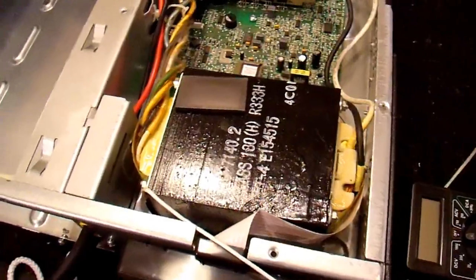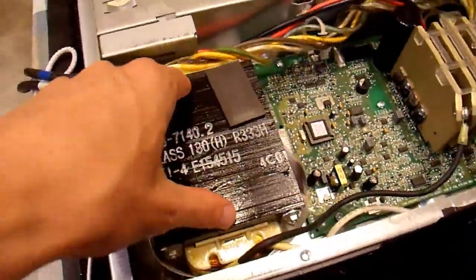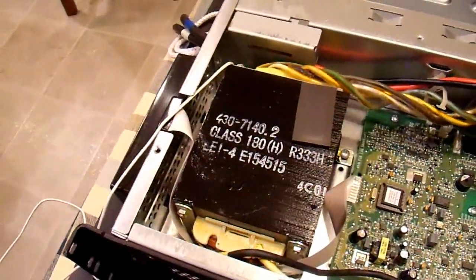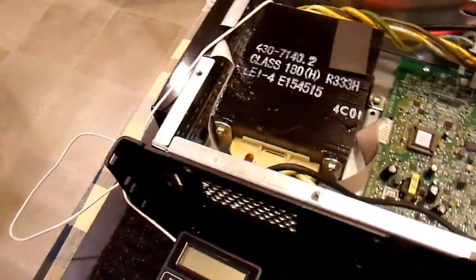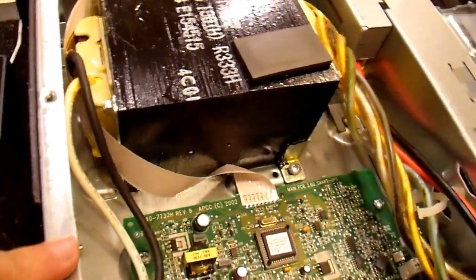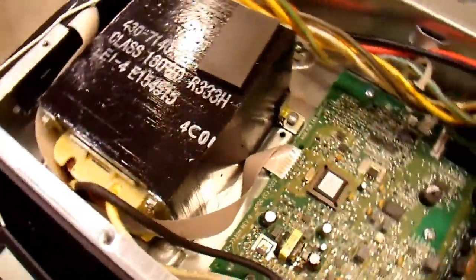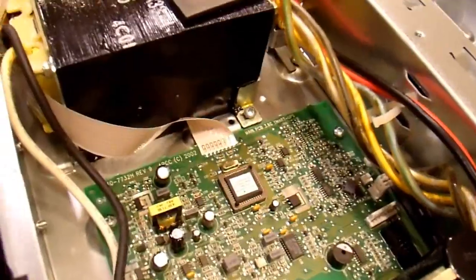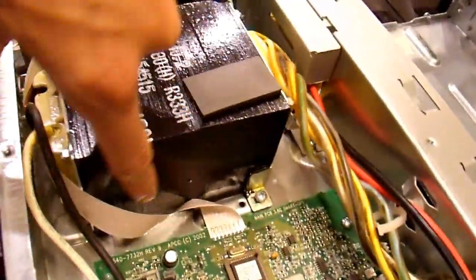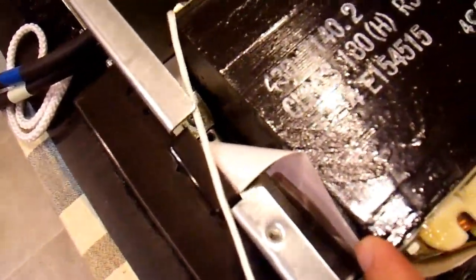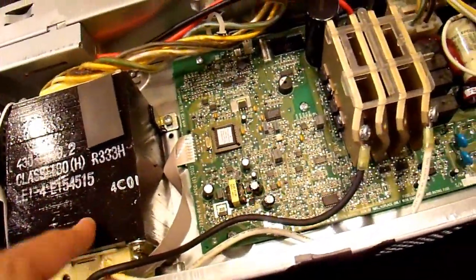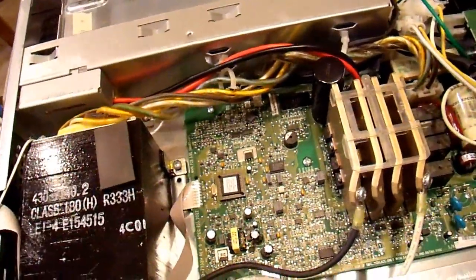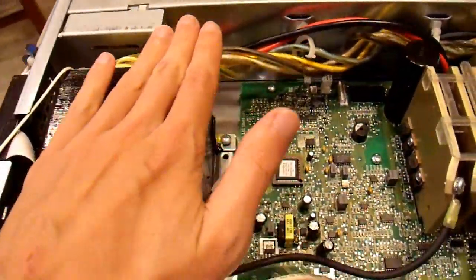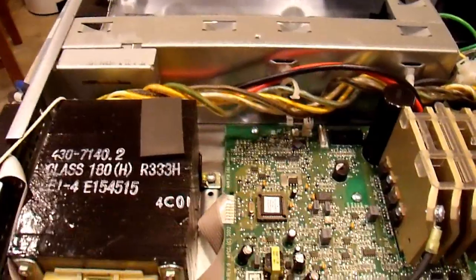So for the first problem, the transformer overheating, I thought a little bit about what to do to keep that cooler. I looked at how it's held into the unit, how the air flows over and under it, and basically the only surfaces that can be cooled by airflow is this surface right over here, and maybe a little bit on the back if the air wraps around. But the bottom, there's no airflow, and the top, there's the metal cover that goes right over it, and you don't get any airflow on top either.